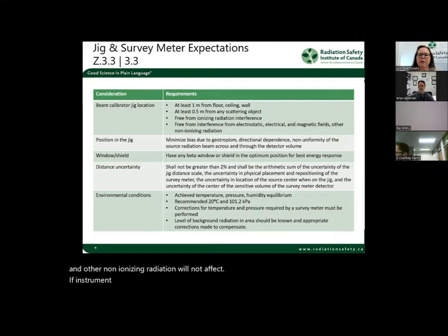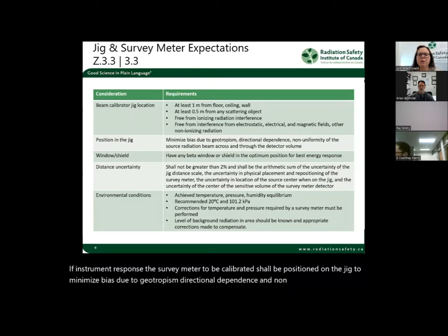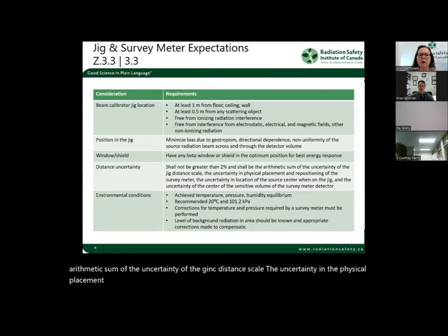The survey meter to be calibrated shall be positioned on the jig to minimize bias due to geotropism, directional dependence, and non-uniformity of the source radiation beam across and through the detector volume. And the survey meter must have any beta window or shield in the optimum position for best energy response. The uncertainty in calibration distance shall not be greater than 2% and shall be the arithmetic sum of the uncertainty of the jig distance scale, the uncertainty in the physical placement and repositioning of the survey meter, the uncertainty in the location of the source center when on the jig, and the uncertainty of the center of the sensitive volume of the survey meter detector.